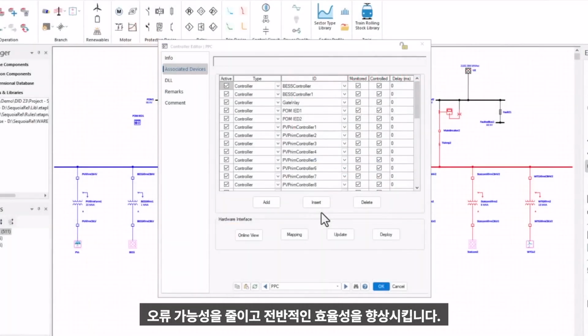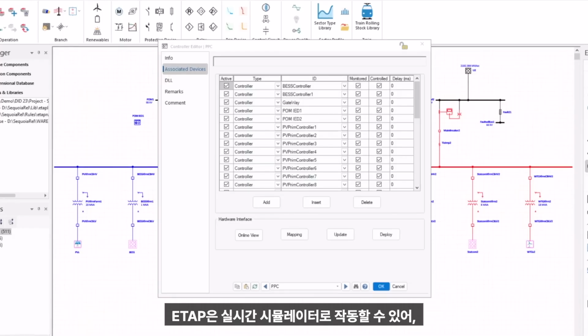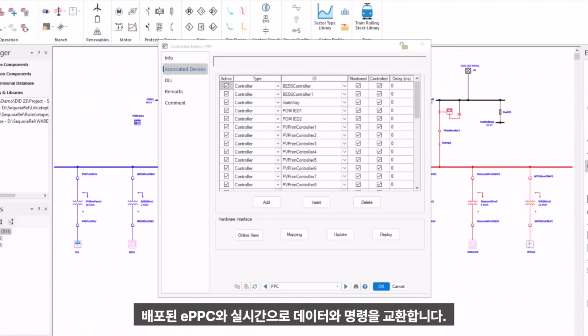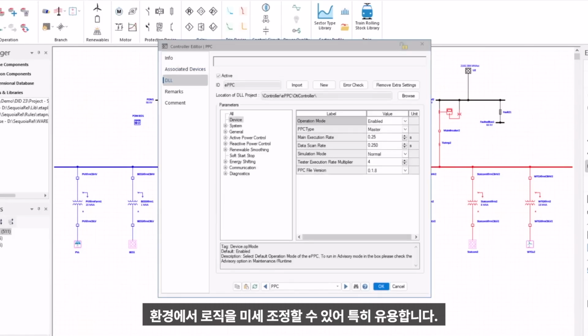The final step in the process is hardware in the loop, or HIL, testing, along with SCADA integration and deployment. This step is what allows us to verify that the control logic developed in ETAP works correctly when connected to real-world systems. ETAP can operate as a real-time simulator, meaning it can continuously exchange live measurement and control commands with the deployed ePPC hardware. This is especially valuable before field deployment because it lets us validate behavior and fine-tune the controller logic in a safe and controlled environment.